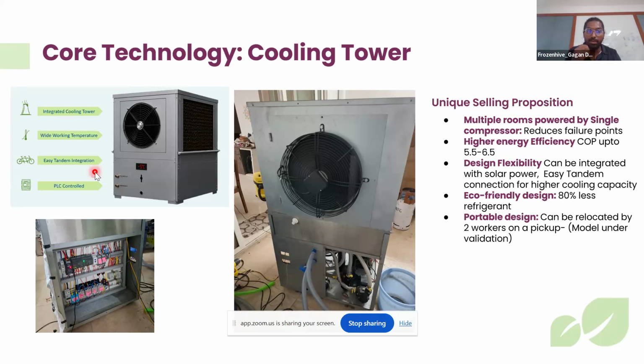It's also able to predict when servicing is required. If there's any major failure that might occur—usually in compressors, if the fan isn't working, the condensers become hot, and we've seen compressors crack due to high pressure and leakage—the system is designed so there's no catastrophic failure. It can predict that things aren't working as expected and that it needs to be serviced immediately, and subsequent alerts are given.